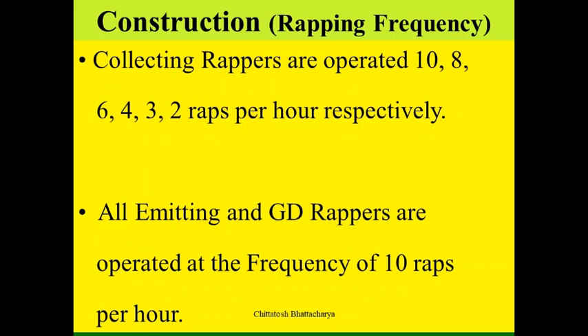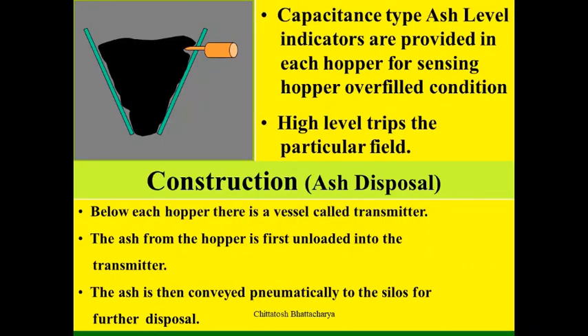Capacitance type ash level indicators are provided in each hopper for sensing the hopper ash level, and high-level trip alarms are provided. For ash disposal, below each hopper there is a transmitter — ash from the hopper is first unloaded into the transmitter and then conveyed pneumatically to the silos for further disposal in the ash dikes.